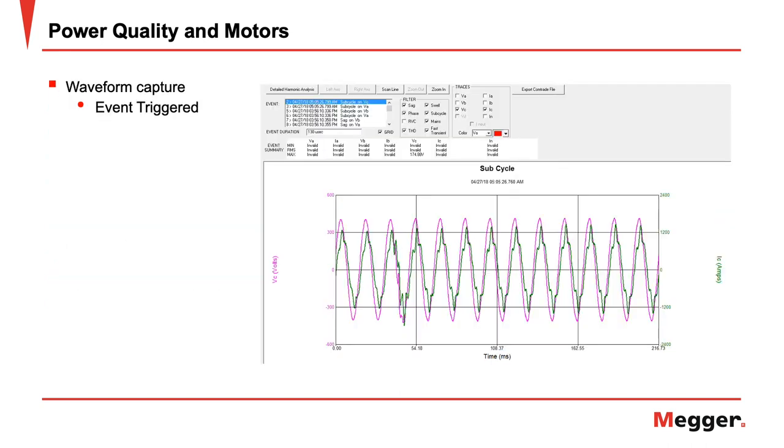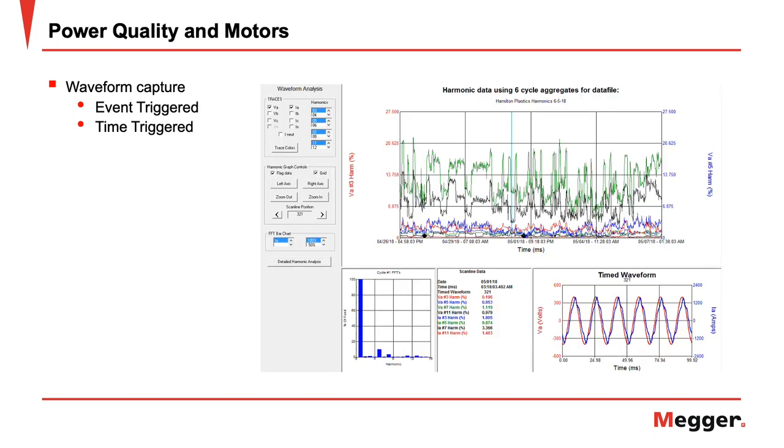The MPQ analyzer will also capture waveforms. Now, these waveforms can be triggered by events. The waveforms can also be triggered by time, and this can be done at the same time, so you can capture both time-triggered periodic waveforms as well as event-triggered waveforms.